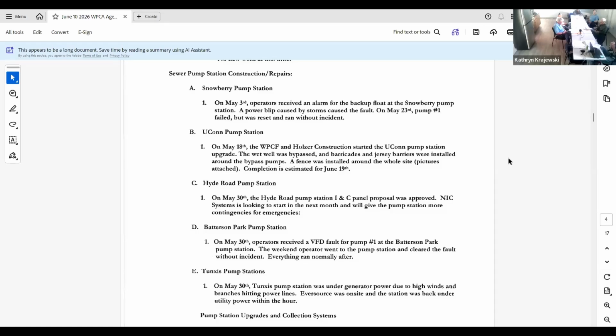I'll go over some pictures of that and what's going on there. Hybrid pump station, we approved the PLC and I&C panel upgrade. So we're starting that this month. And that was what I was referring to last month, where if the PLC fails like it did 2 months ago, the ultrasonic transducer will take over level control. It just gives us more fail safes for emergencies.